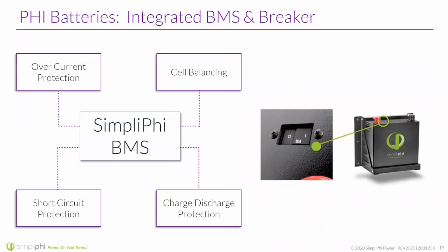It does do some level of overcurrent, short circuit, charge and discharge protection, but it is not to be relied upon for those things. If you push the battery too much, you will harm the battery. So if you size way incorrectly, the battery management system is not going to be able to protect over and over and make sure that the battery does not get damaged. So keep that in mind when it comes to this stuff.